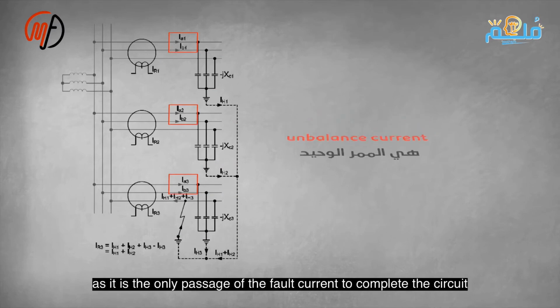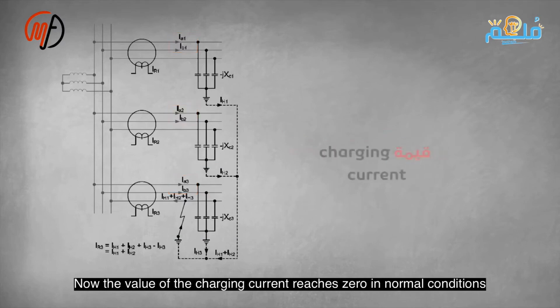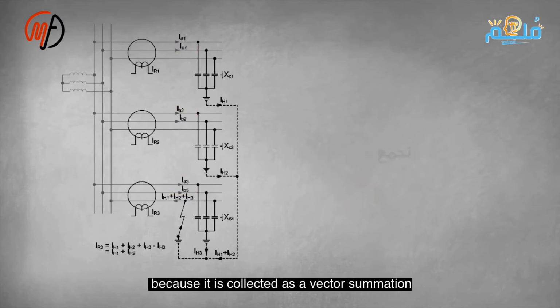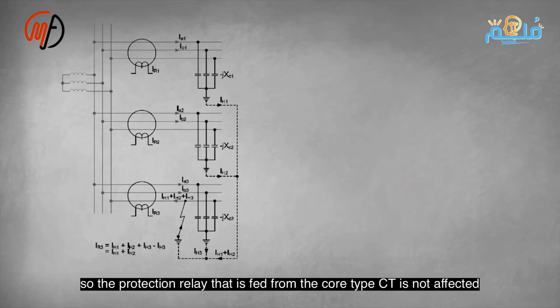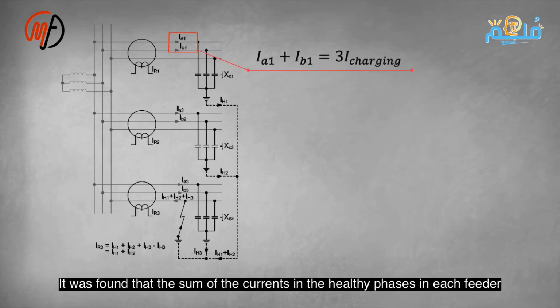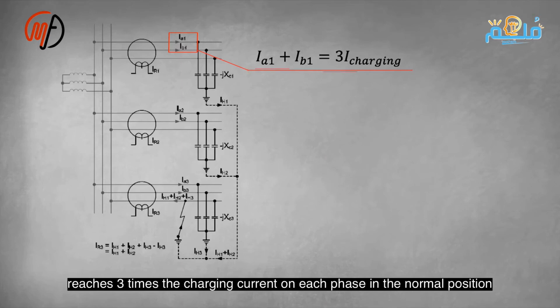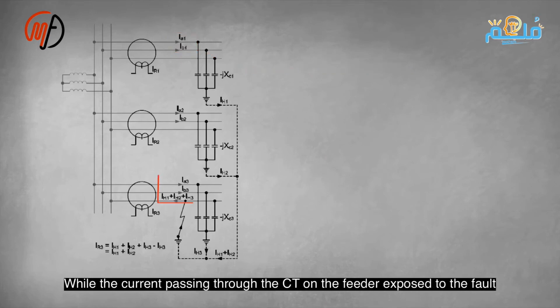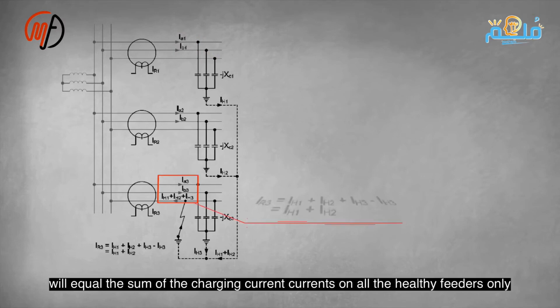The sum of currents in the healthy phases per feeder is three times the charging current per phase normally, while the current through the CT on the faulted feeder equals the sum of charging currents on all healthy feeders. The protection relay is fed from the core balance current transformer. Thus, the current through the CT on the faulty feeder equals the sum of charging currents on all healthy feeders.